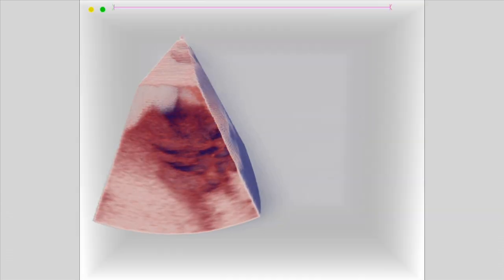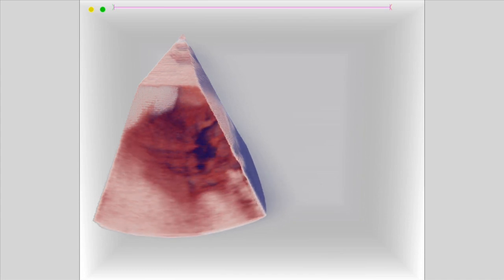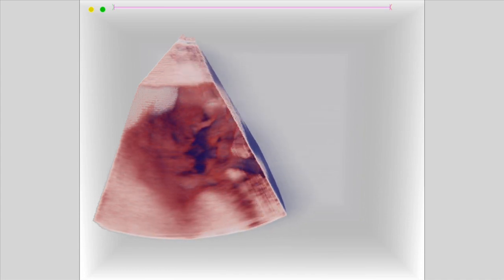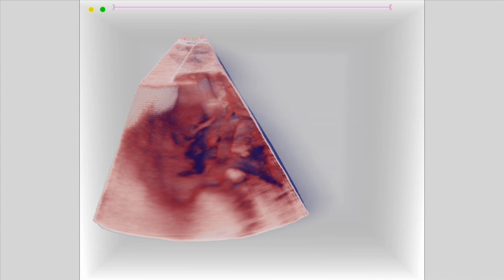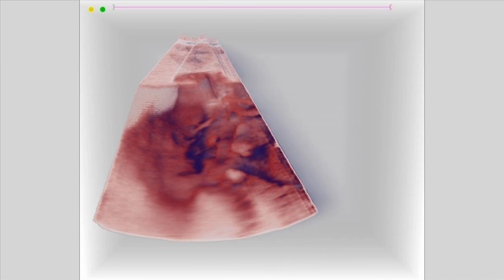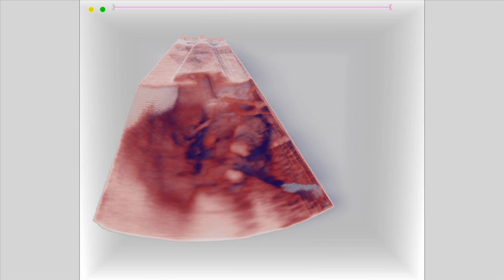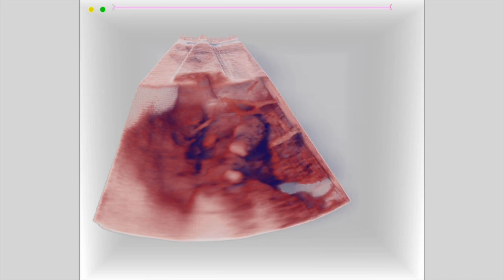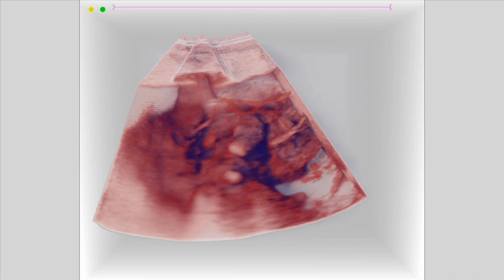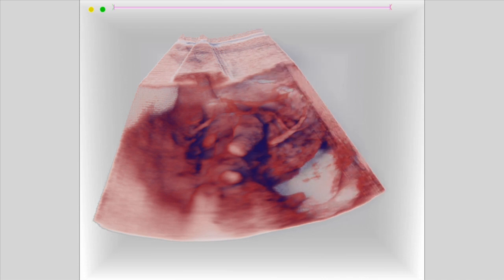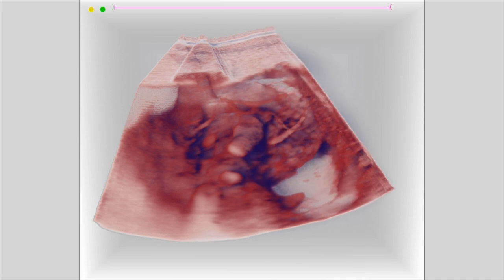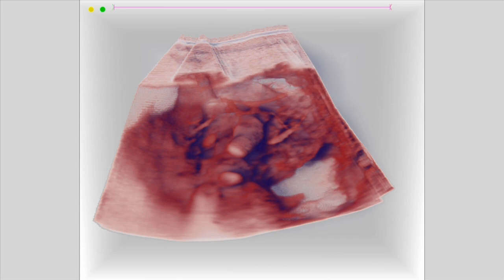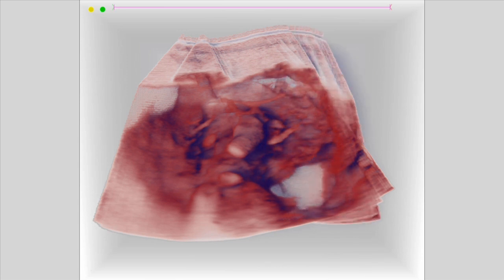The second enabling technology in this project is an image-based registration algorithm that fits together the current volume with the previously acquired volumes from the stream. If the frame rate is high enough, there will be enough overlap in the streamed volumes to create a big volume, which we will call a compound volume, that can cover a large anatomical object, like for instance the liver.